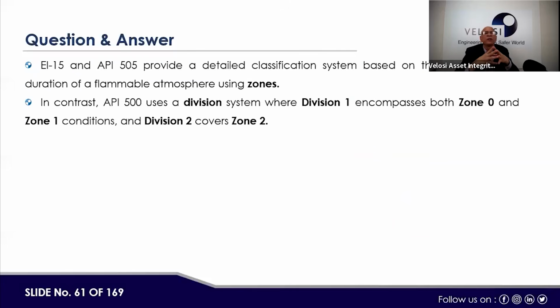So this is the answer. EI-15 and API 505 provide a detailed classification system based on the likelihood and duration of the flammable atmosphere using zones, right? In contrast, API 500 uses the division system, where division 1 encompasses both zone 0 and zone 1 conditions, and division 2 covers zone 2. So EI-15 and API 505 use zone 0, zone 1, zone 2, whereas API 500 uses only division 1 and division 2.